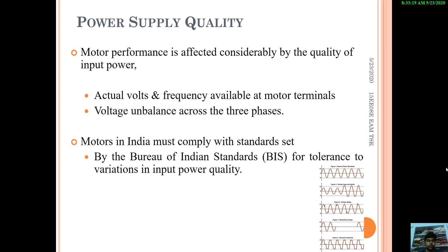Voltage unbalance can occur across the three phases. That is, the three phases will experience a voltage unbalance impact, which will decrease the motor performance. And the tolerance to variations in input power quality is specified by the BIS, the Bureau of Indian Standards. The BIS standards specify a voltage variation of plus or minus 6% and a frequency variation of plus or minus 3%. If it is within 6% and 3%, this won't cause any damage or collapse in a motor.